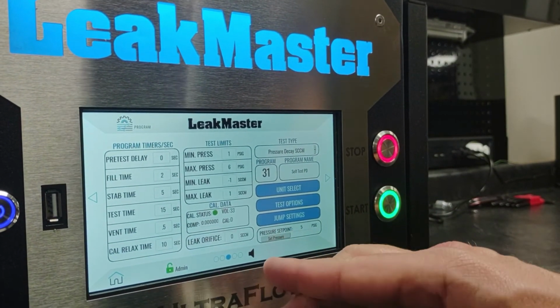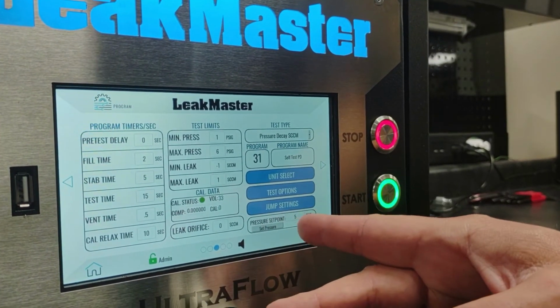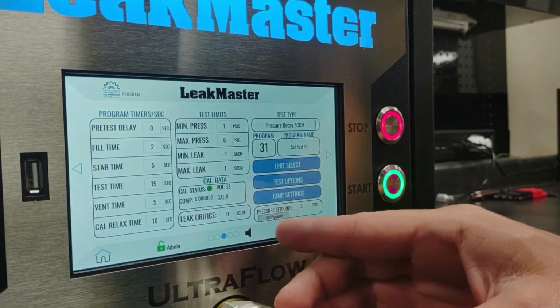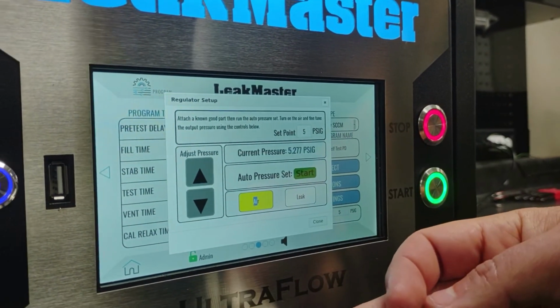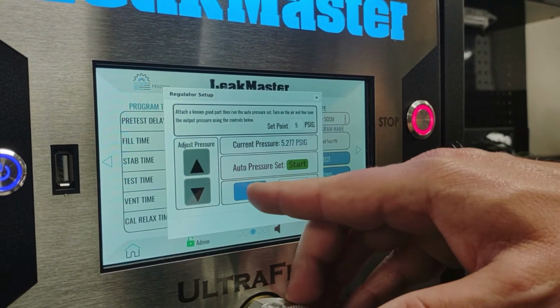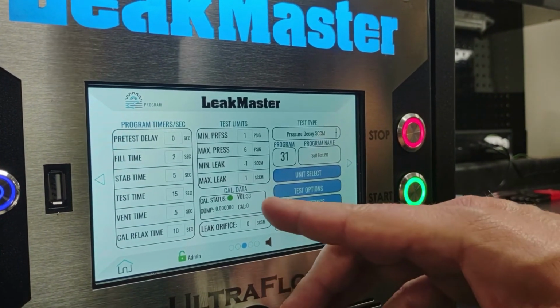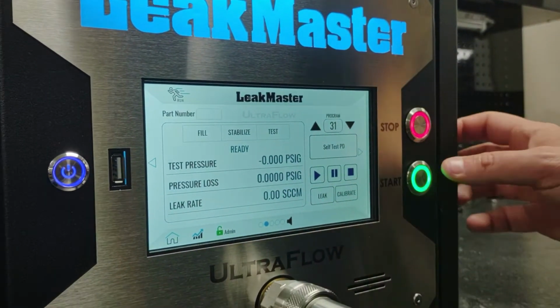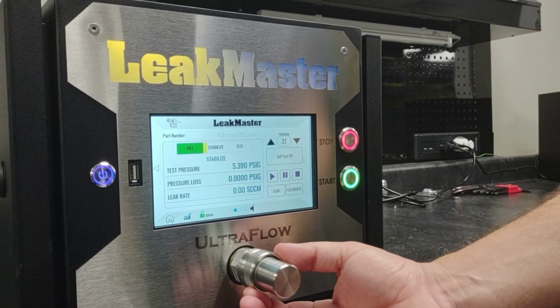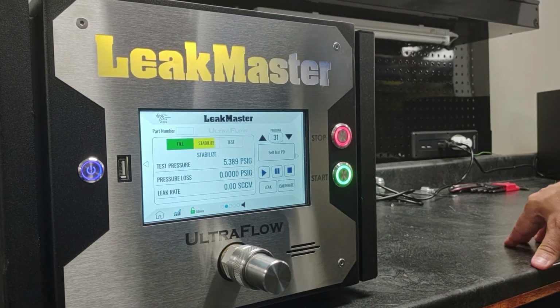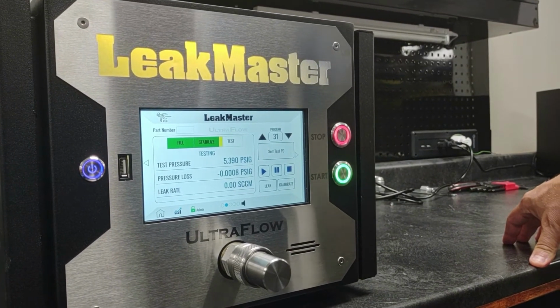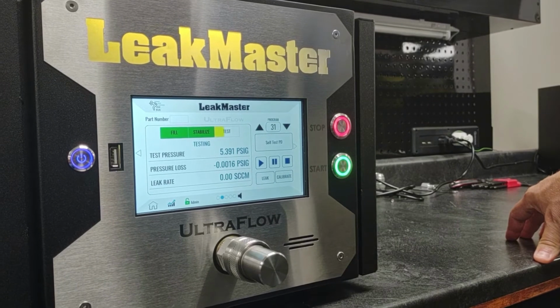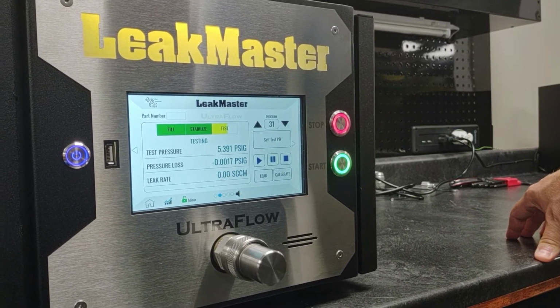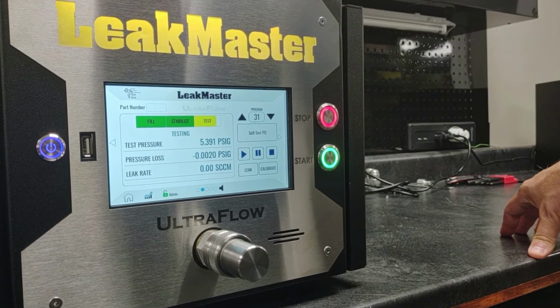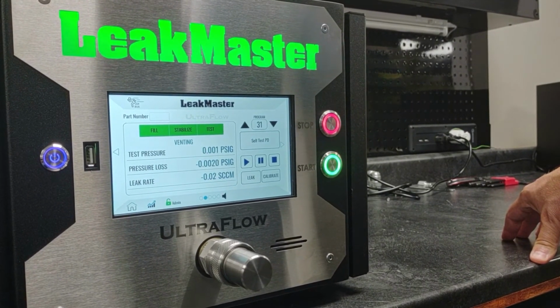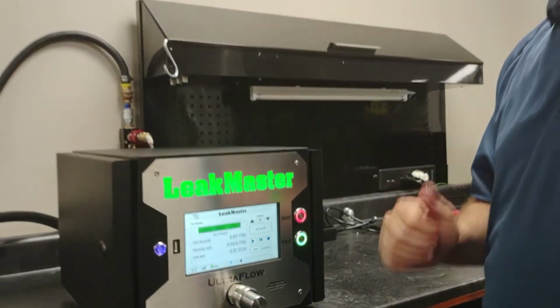The first thing we're going to do is come in and set our test pressure. This is already set by default to 5 psi for this self-test. If I come in to set pressure, I can hit air. It's going to deliver air to this port, and it's going to verify that we have 5 psi there. At this point, I can come out and I can run this test. All we're doing is testing the internal manifold here to ensure that this guy is leak-free. So 0 leakage, that's perfect. We know we're good to go.